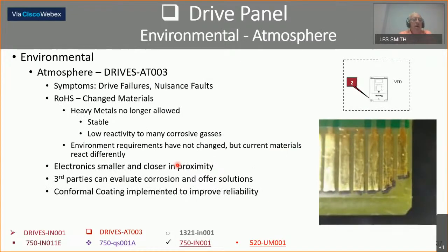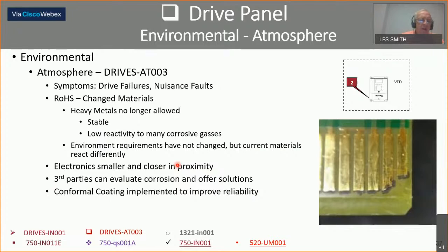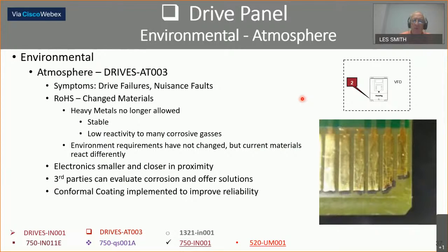Regarding the environment: symptoms of drive failure are nuisance faults. ROHS — R-O-H-S — has changed the materials in drives; they've taken heavy materials out. When they removed the heavy metal, the drives are not as hearty in harsh environments. We now have smaller circuits and conformal coating, but these drives won't stand up as well as older drives — and that's not just one brand, that's all brands. The circuitry has gotten much finer. So be aware of that: keep them cool, keep them away from contaminants. Protect the cooling fans and do not expose to corrosive atmospheres — this statement appears in both the 520 and competitor's drives. Keep the drive's environment friendly to the drive.